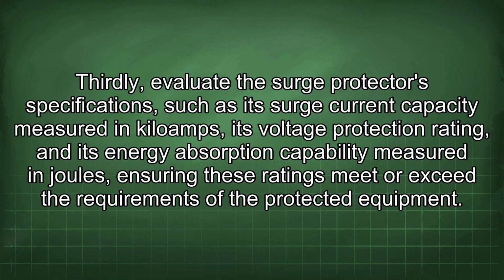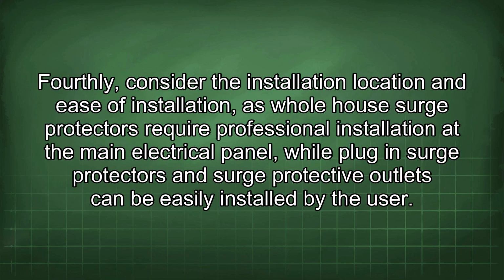Thirdly, evaluate the surge protector's specifications, such as its surge current capacity measured in kiloamps, its voltage protection rating, and its energy absorption capability measured in joules, ensuring these ratings meet or exceed the requirements of the protected equipment. Fourthly, consider the installation location and ease of installation, as whole house surge protectors require professional installation at the main electrical panel, while plug-in surge protectors and surge protective outlets can be easily installed by the user.